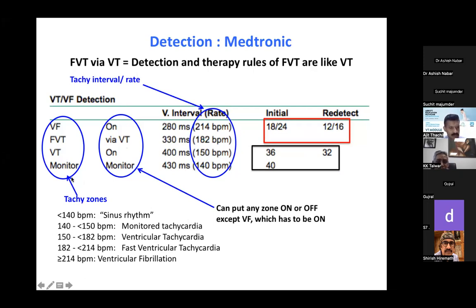So let's see what all these numbers mean. Anything less than 140 beats per minute, going on for 40 beats, is called a sinus rhythm. Anything between 140 to 150 beats per minute, continuing for 36 beats, is called a VT in the monitor zone. Anything between 100 and 182 beats per minute, if it is 18 out of 24, I'll just explain what 18 out of 24 is. No, sorry, this is via VT, meaning the rule for fast VT is like VT. So anything between 150 to 182, going on for 36 continuous beats, because it's via VT, is called a fast ventricular tachycardia. Anything above 214 beats per minute, satisfying the 18 out of 24 rule, is called a ventricular fibrillation.